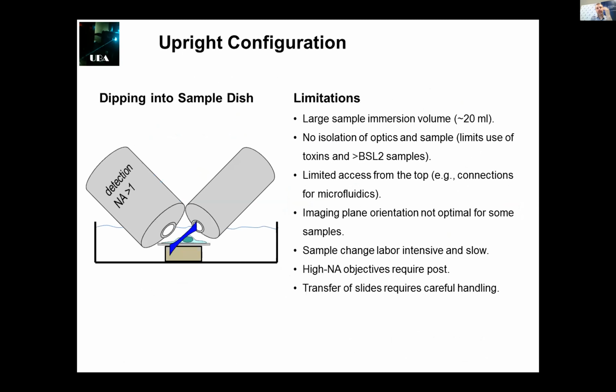So if this is wonderful, why do we want to stress or do something different? Well, as I said at the beginning, it has some constraints. It is difficult to accommodate this large detection objective, and we need to place our sample in some kind of a post, because the light sheet cannot get to the bottom of a sample chamber. For that reason, it was one of the main difficulties we found in order to work in a regular configuration. But also we need to immerse our objective here, and this limits our possibilities to use, for example, toxins that can be hazardous for us, or they can distort or break the optics that we have here.